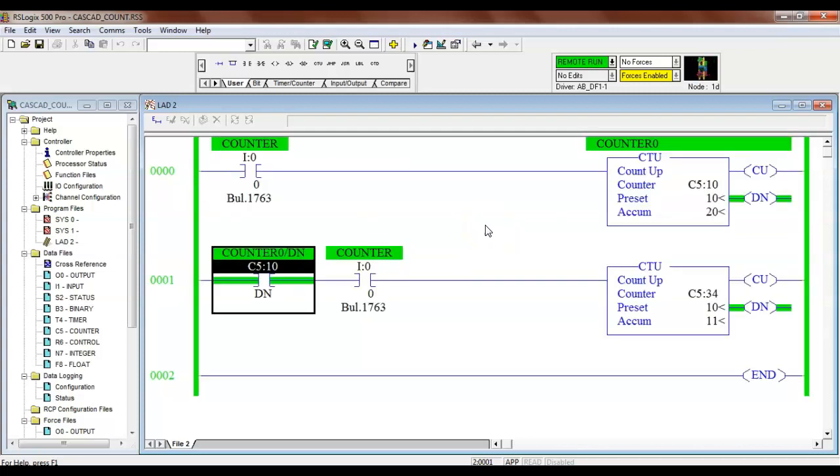So it seems like that's a big deal, but what we're dealing with is 32,767, and it is for RSLogix 500. Of course, this is the thing that they took care of on newer PLCs. So newer PLCs, we can specify counters with 64-bit signed numbers, double words, which probably will count more than any company would ever need.